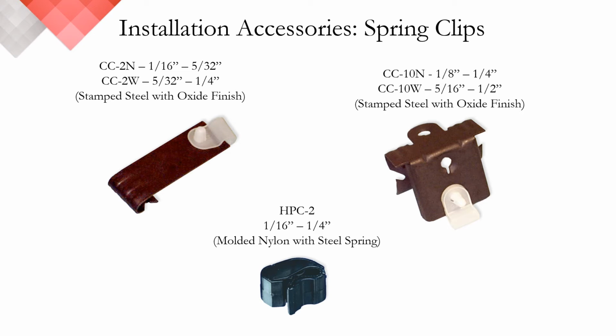The Protectowire company offers an assortment of approved fasteners and splicing devices to facilitate installation for both standard and special applications. Protectowire approved fasteners are generally designed to lightly clamp the detector, which enables the tension to be applied progressively. This method is better than arrangements which apply a high tensile load at the end of each run or clamp and compress the sensor so tightly that the inner insulation becomes damaged. To ensure a trouble-free installation, only factory-approved fasteners should be used. The use of non-approved fasteners may physically damage the detector, thereby causing false alarms, and in some cases, void the detector's warranty.